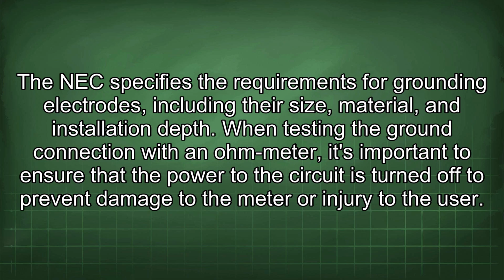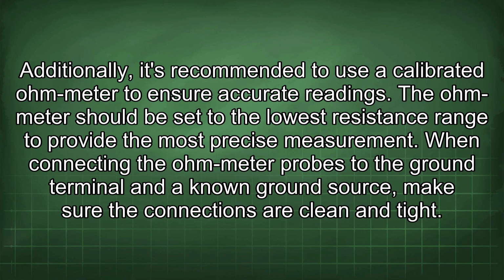When testing the ground connection with an Ohm-Meter, it's important to ensure that the power to the circuit is turned off to prevent damage to the meter or injury to the user. Additionally, it's recommended to use a calibrated Ohm-Meter to ensure accurate readings. The Ohm-Meter should be set to the lowest resistance range to provide the most precise measurement. When connecting the Ohm-Meter probes to the ground terminal and a known ground source, make sure the connections are clean and tight.